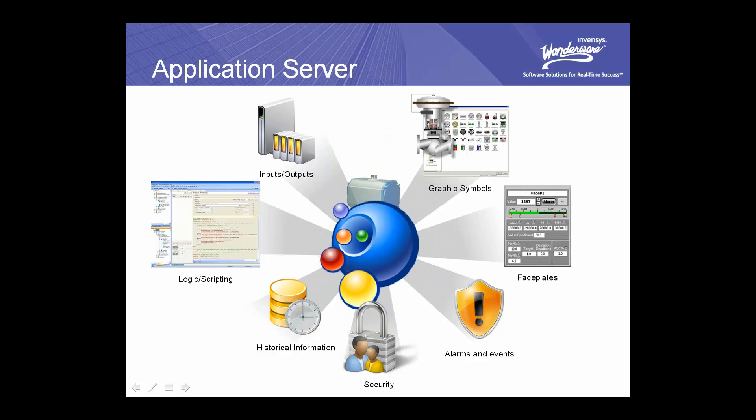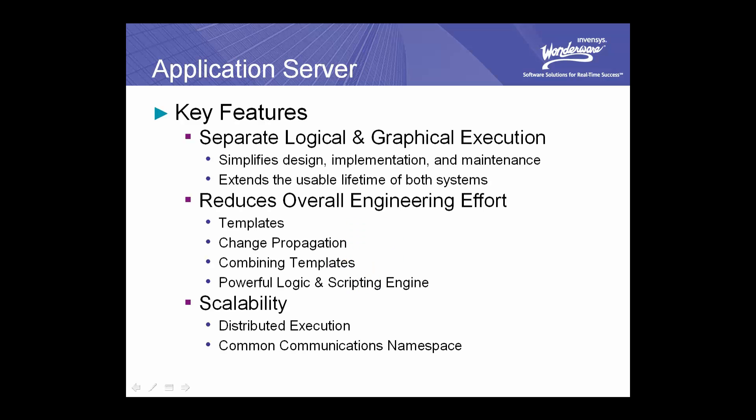That's one of the key benefits of Application Server. By separating these functions — the supervision from the visualization — we're able to simplify the design of each component by focusing each on what it's supposed to do, not mixing them all together. Because they are separated, we also realize a simplification in implementing, and we are more easily able to maintain the system because changes in one do not necessitate a change in the other. Coupling these things together, the usable lifetime of the application is greatly extended.